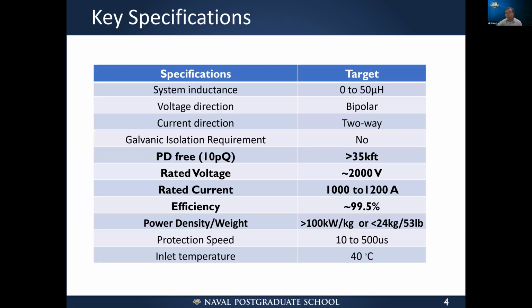So these are the key specifications we received from NASA. The system inductance is about 0 to 50 microhenry. It depends on the fault locations and also the location of the solid state circuit breaker. It should be a generic solid state circuit breaker, which means it can block bipolar voltage and carry bidirectional current. There's no need for galvanic isolation at breaker level, and it should be PD-free at altitudes higher than 35,000 feet. The rated voltage of the system is about 2 kilovolts and the rated current about 1,000 amps.